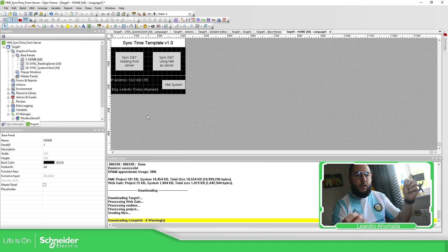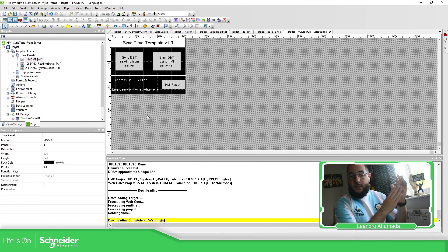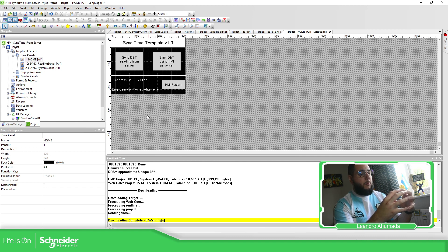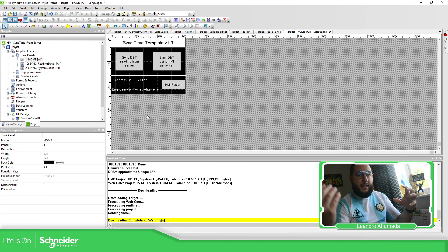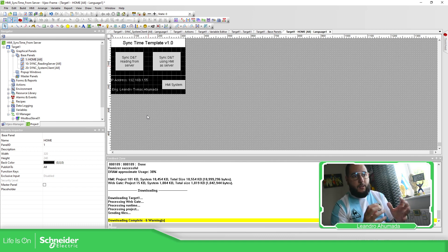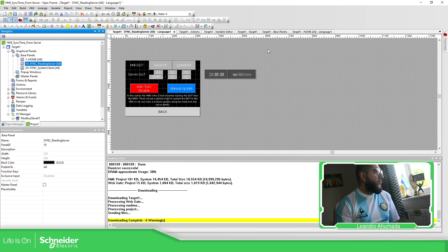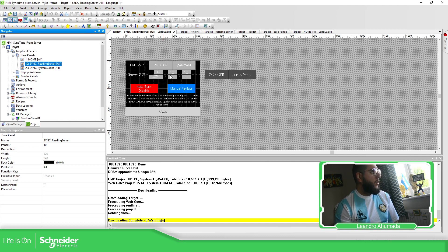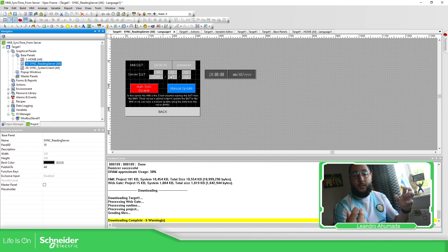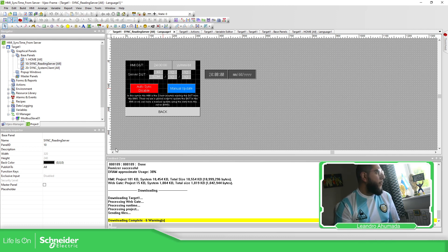In this example, I'm using the HMI as a master or client in a TCP communication model, with the server or slave, in order to read the data from the HMI to the target and receive the date and time parameters. The other option is the HMI has internal registers, and the client — my PLC or system — writes information to it for the HMI to update the values. The first one is reading from the server, where the HMI is the master and the PLC is the slave.